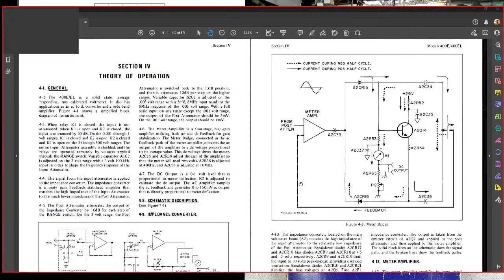So we go through an impedance converter, post attenuation, meter amplifier, obviously some tuning parts in there, and a meter bridge to drive the meter, and then a buffer to take the meter amplifier output as the AC output. So the impedance converter is really the high impedance source that creates a low impedance drive internally, right? Yeah, I'd say it's basically a buffer, and that's how they've drawn it. It's like a non-inverting amplifier with zero gain, straight up negative feedback to make the gain equal to 1, or 0 dB gain.